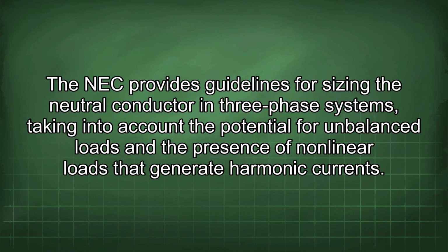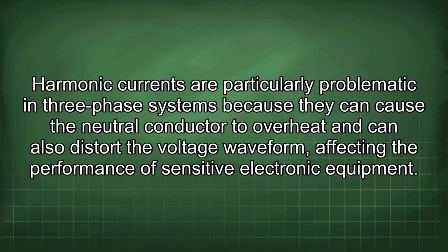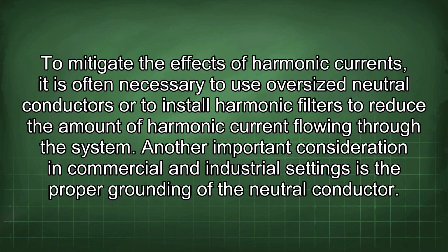The NEC provides guidelines for sizing the neutral conductor in three-phase systems, taking into account the potential for unbalanced loads and the presence of nonlinear loads that generate harmonic currents. Harmonic currents are particularly problematic in three-phase systems because they can cause the neutral conductor to overheat and can also distort the voltage waveform, affecting the performance of sensitive electronic equipment. To mitigate the effects of harmonic currents, it is often necessary to use oversized neutral conductors or to install harmonic filters to reduce the amount of harmonic current flowing through the system.